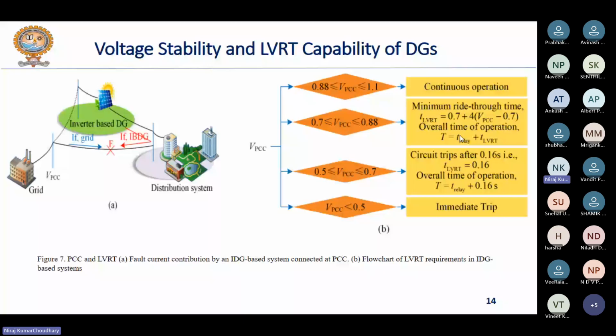Now, here another thing is that if the voltage is in between 0.5 to 0.7, then the overall time of operation will be T relay plus 0.16, means your DG should be disconnected from the system if the time of operation is equal to or above this value, T relay plus 0.16 second. And then as per the IEEE standard 1547, DG should be disconnected from the system immediately if the voltage of the point of common coupling bus falls below 0.5 per unit, right? So this is another important factor that should be considered while solving the relay coordination problem.